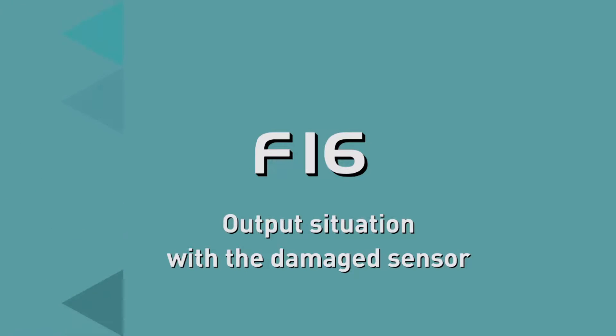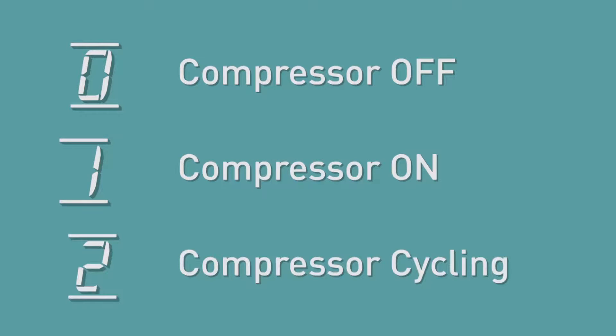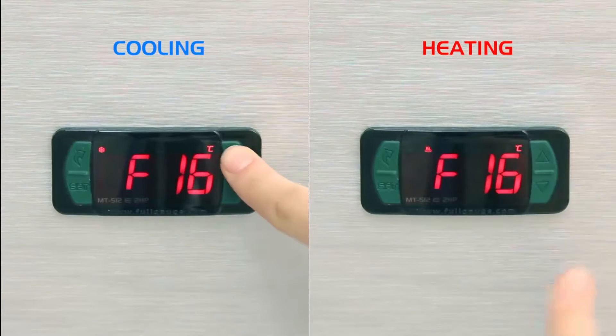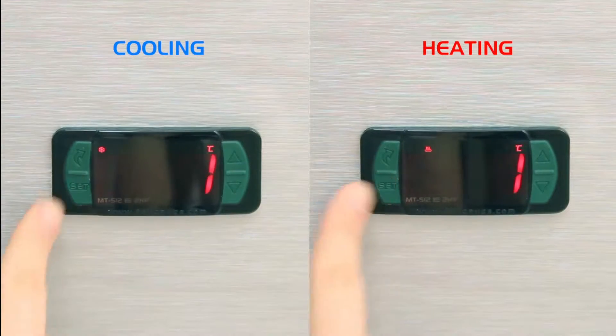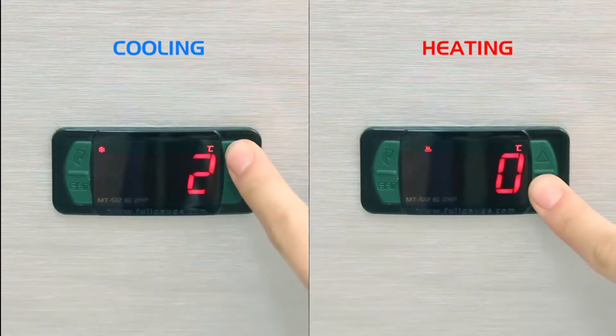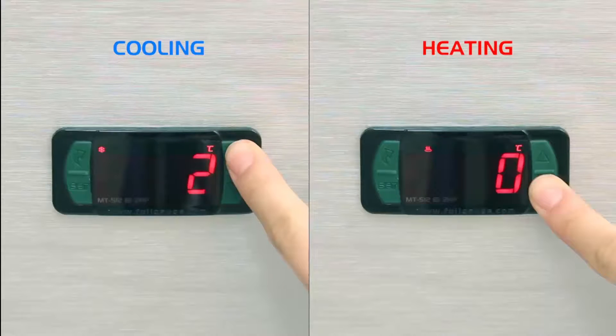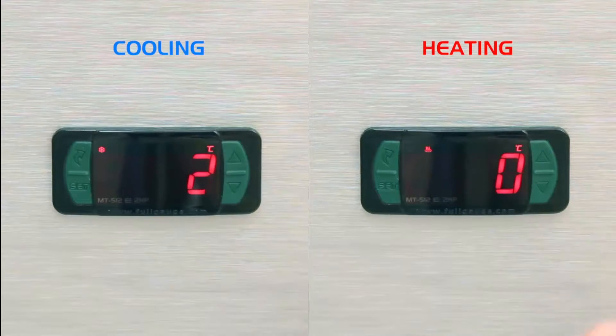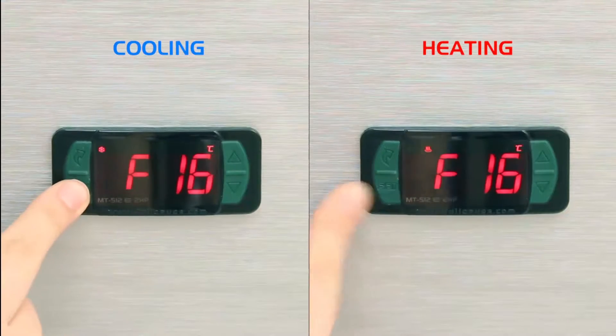F16, Output Situation with Damage Sensor. 0, to leave the compressor off. 1, to leave the compressor on. 2, to keep the compressor cycling according to time set in parameters F17 and F18. This was the option adopted in the example. If when operating in heating there is a problem with the sensor, the output is switched off.